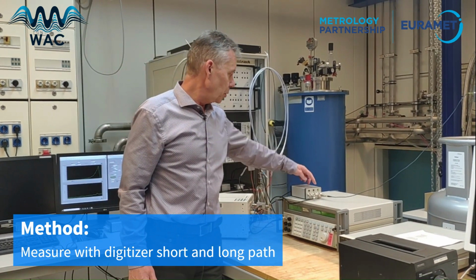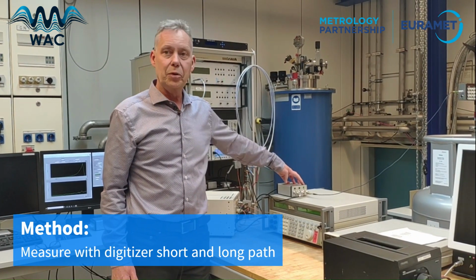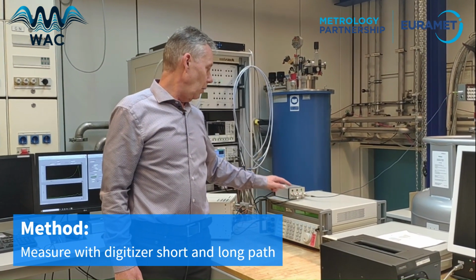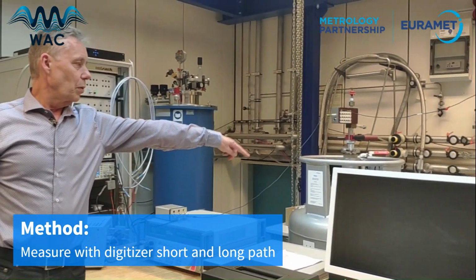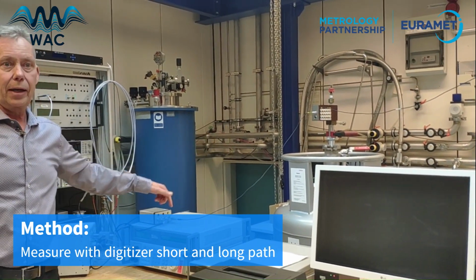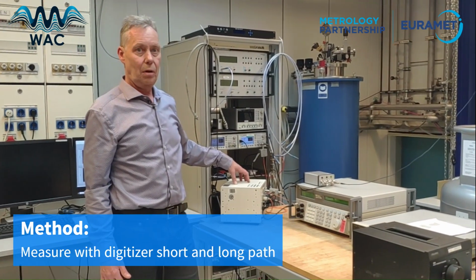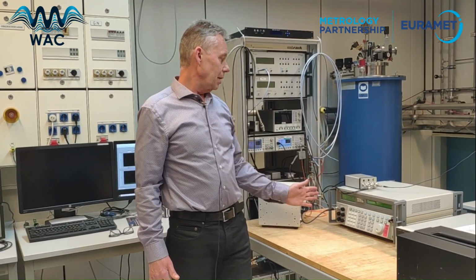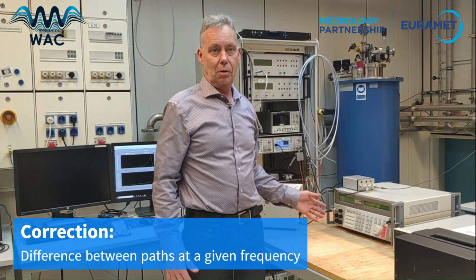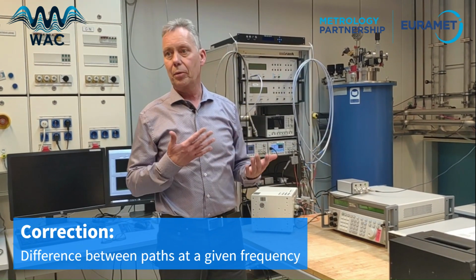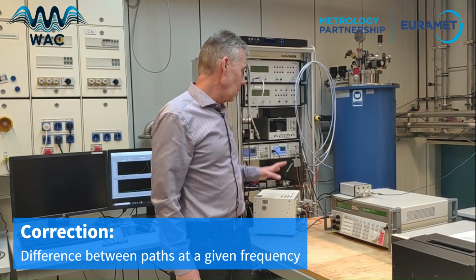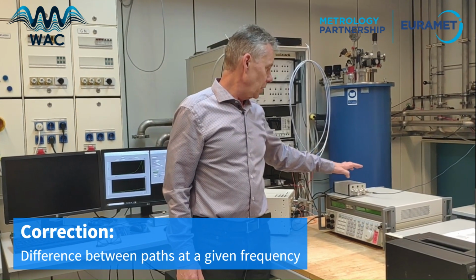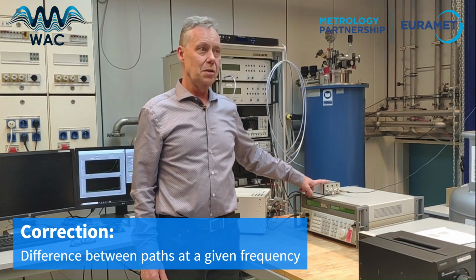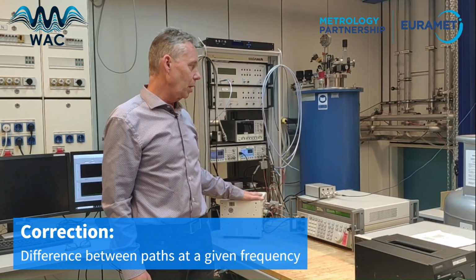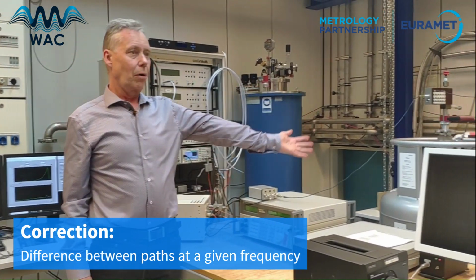If we switch to the other position, as we see now with the green light, we go all the way down to the Josephson array and then back to the digitizer. By setting a specific frequency with an amplitude of 1 volt, or whatever we like to investigate, we can see the difference when switching between the two positions of the switch. We can see the short cable in relation to the long cable to the Josephson system.